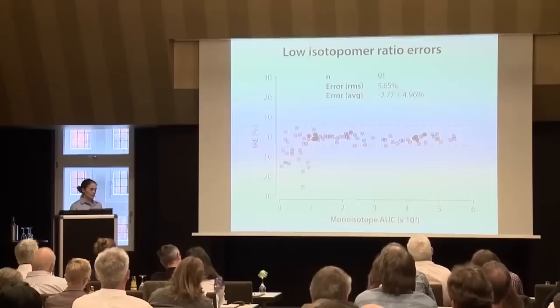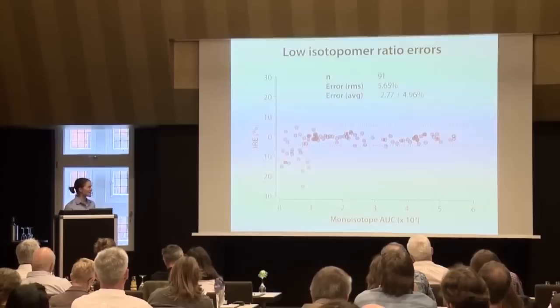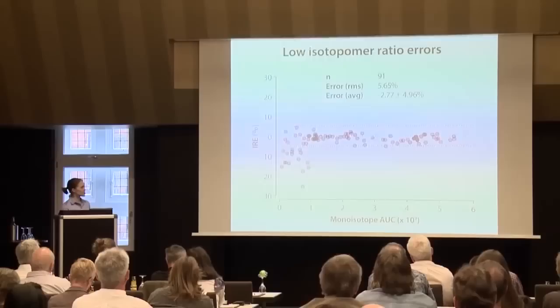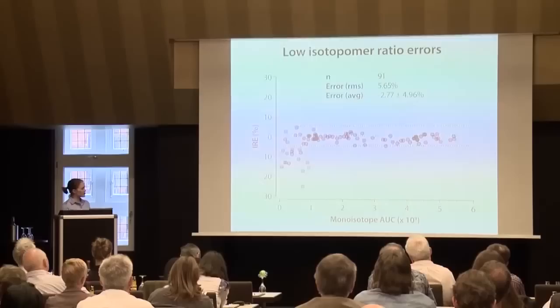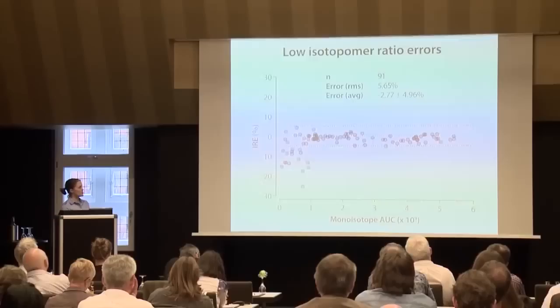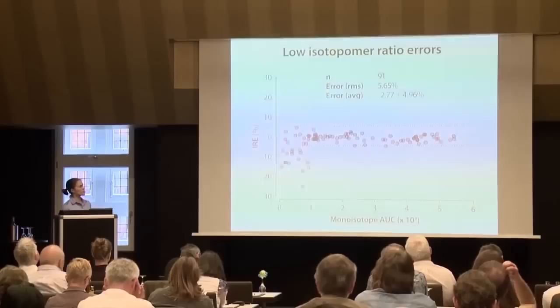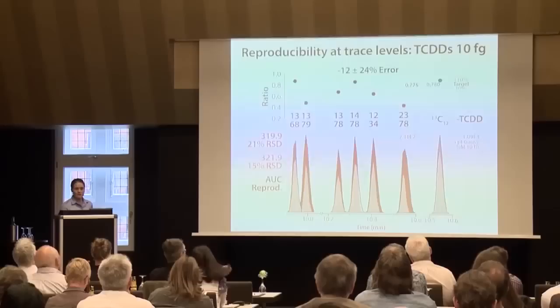Also important, when we get into many of the EPA-based methods that we like to run, are isotopomer ratio errors. Here I've taken those 93 compounds and looked at the isotopic ratio error. It is, of course, related to the intensity of the ion itself, but above a certain threshold, we are in general having errors less than, on average, 3%.